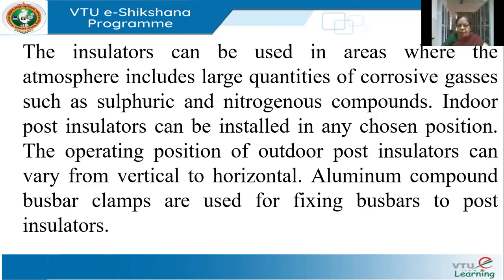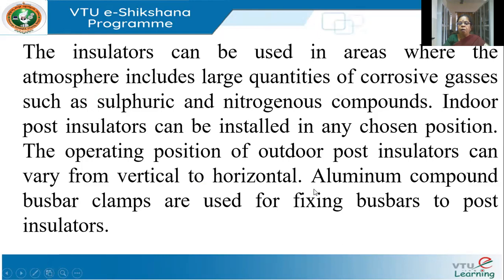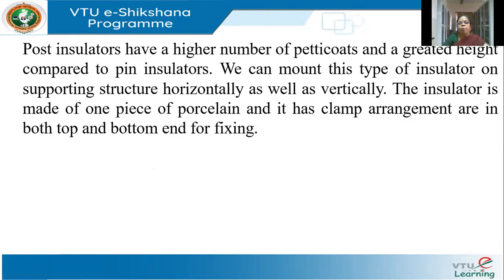If you use it indoors, like in an indoor switch yard, you can mount it both horizontally or vertically. The ends have clamps at both ends and you can use them for fixing bus bars to the post insulators. You can mount it on the supporting structure — the pole or the tower — in both horizontal or vertical position. It is made of a single piece of porcelain and, unlike a pin insulator which has a pin only at the top, this has a clamp arrangement both at the top and the bottom for fixing.